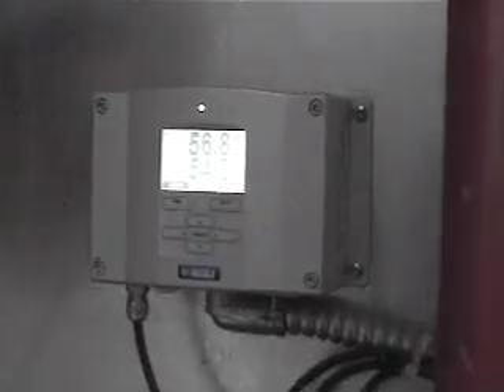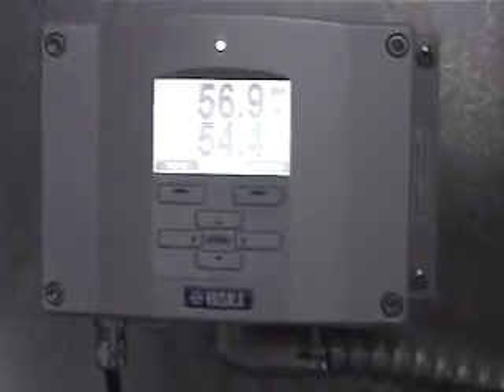Where are the freezestats? Let's go to the air sensor here for the building, and it also measures your humidity. That one sensor does both of them? Yeah. That's new. Yeah, this is a Vaisala device. So you actually have a digital readout of what you've got as well. And then what does it send back to the controls? Just a 0 to 5 volt signal for each of them. You just calibrate it to... Yeah, they gave us the ranges for the temperature, and then the humidity is 0 to 100%. Wow, it's kind of nice. Yeah, it's a Cadillac device.